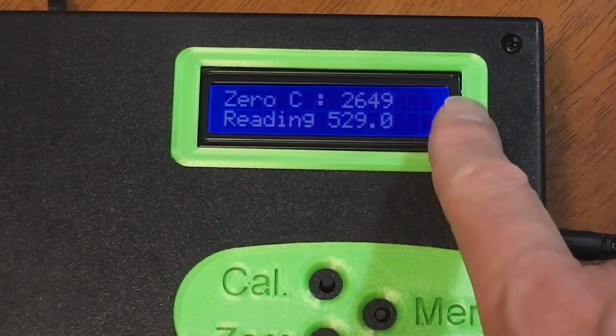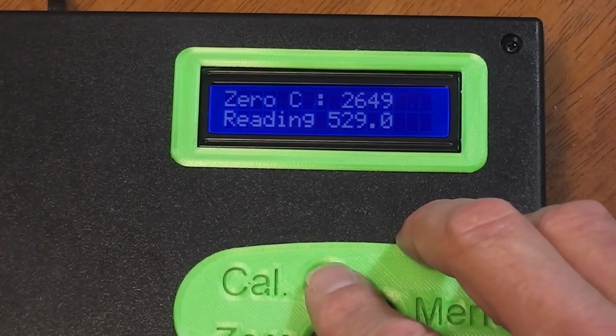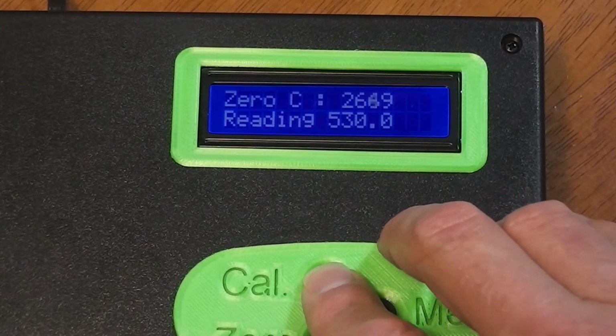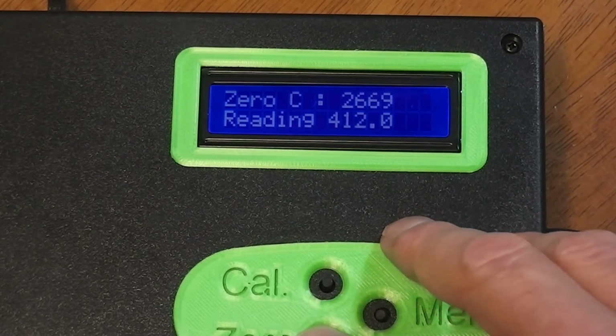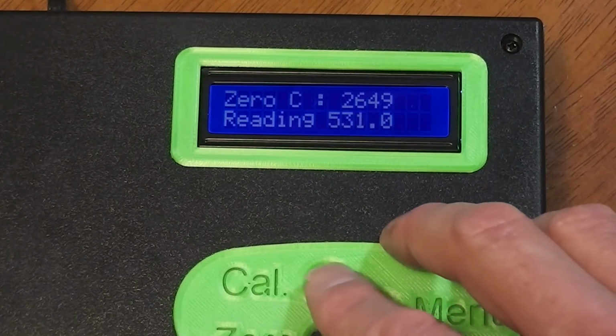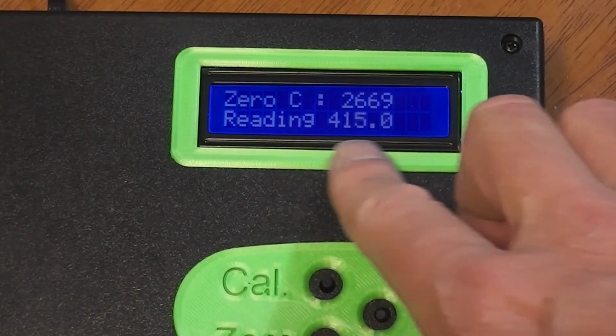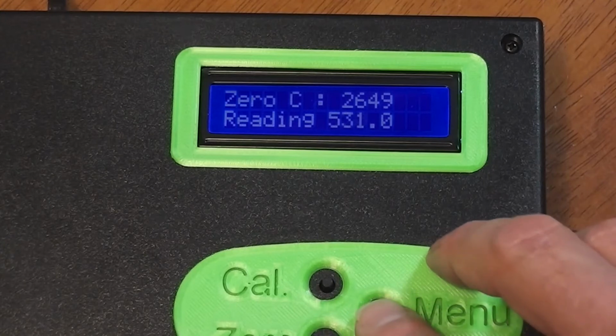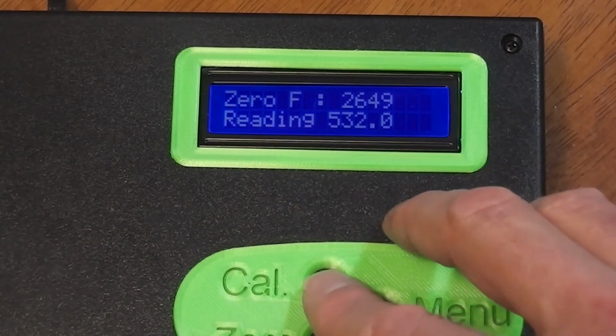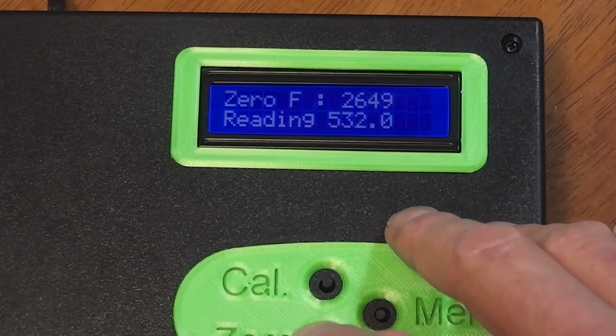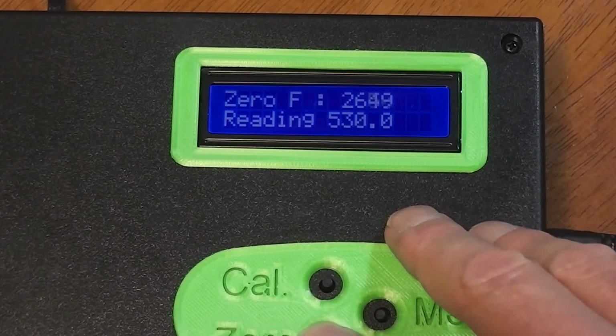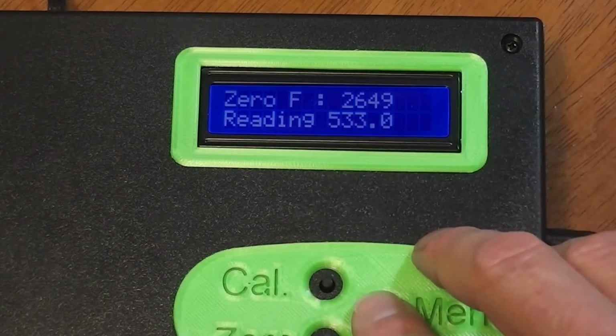Now this is for zeroing it. You probably never really need to do that. That's what the calibration's for. So we can see that if we make a change on the 0 reading, the actual reading of the unit itself changes quite dramatically. That's a coarse adjustment. We have a fine adjustment. And you can see the reading changing for that.